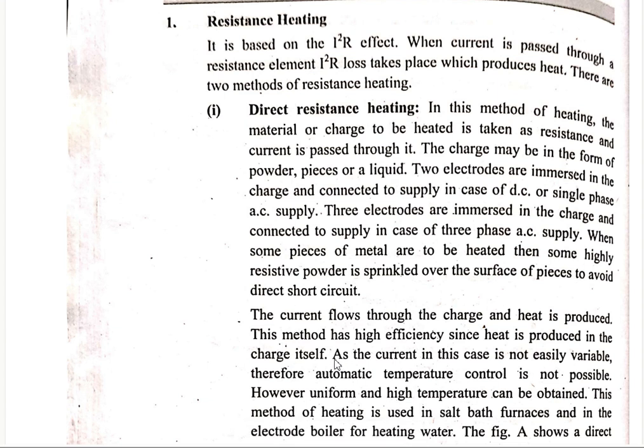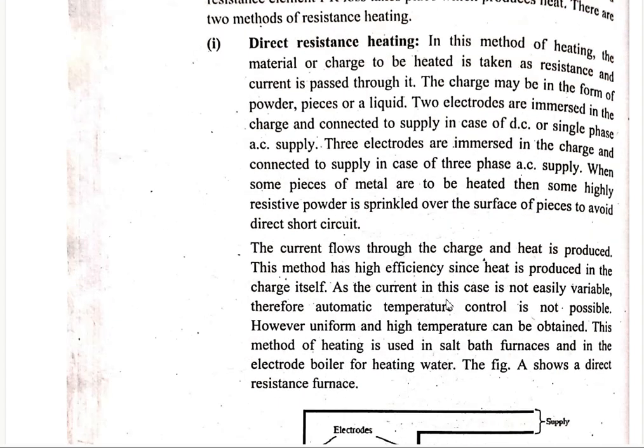This method has high efficiency since the current flows in the charge itself. However, the current is not easily variable, so automatic temperature control is not easily possible in direct resistance heating. However, automatic temperature control can be obtained with certain configurations.